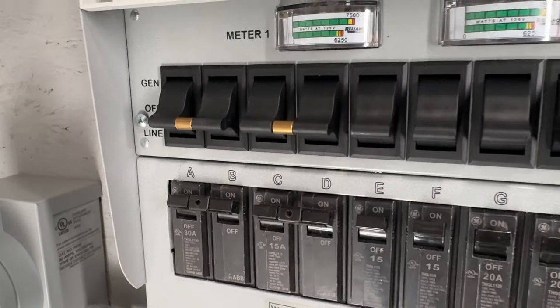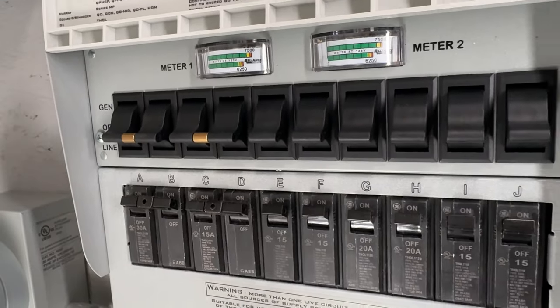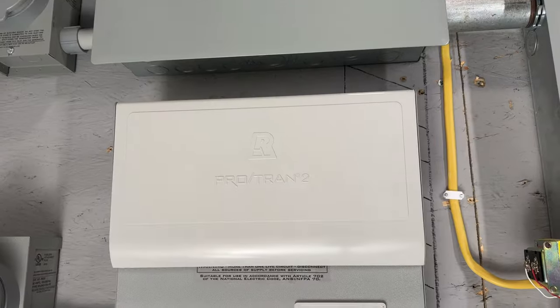Once you flip that breaker, all of the circuits are either running off of grid or they're running off of battery power. For something that's a little more nuanced, you can get a transfer panel. A transfer panel allows you to switch individual breakers between grid and battery power.